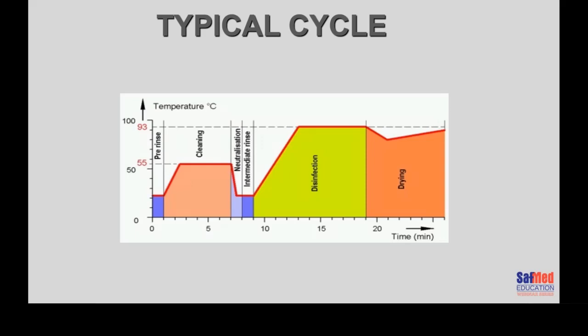After the wash phase, depending on the setup, if you're using alkaline-based detergents you may have to neutralize them. Then the instruments are rinsed. Then there's a disinfection phase — in that phase, referring to the temperature on this particular chart, they're referring to 93 degrees. That's called the AO relationship — the temperature at which disinfection takes place — and that's a variable. It can be at a higher temperature for a shorter period of time, or a slightly lower temperature for a longer period of time. The very last phase is the drying cycle.